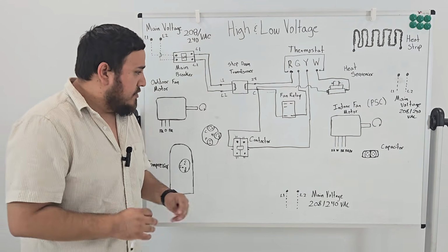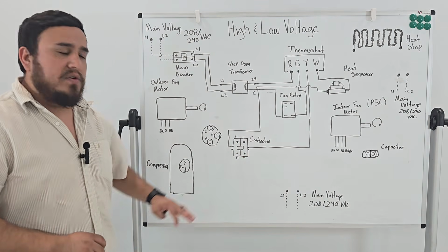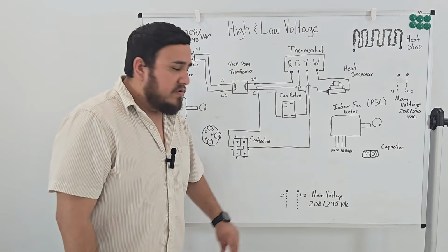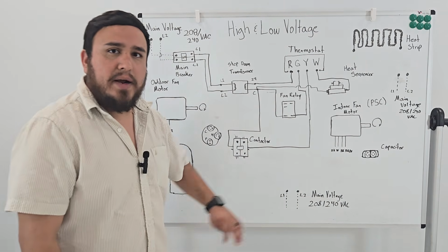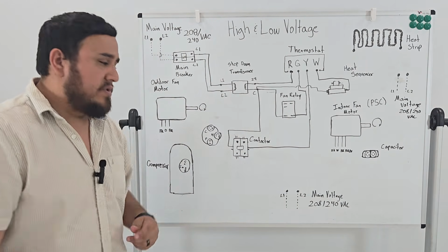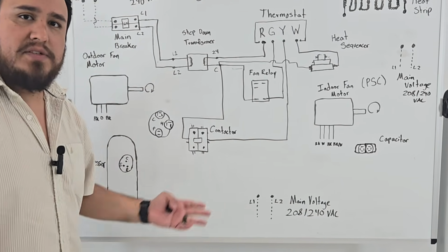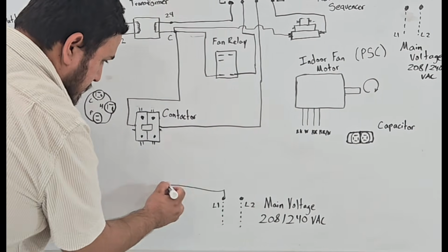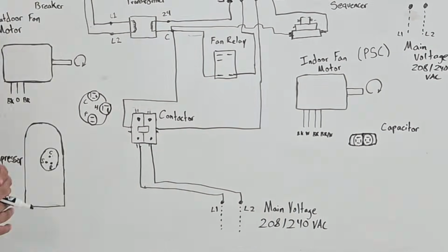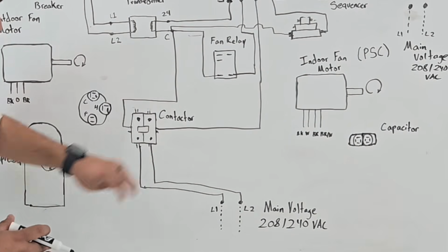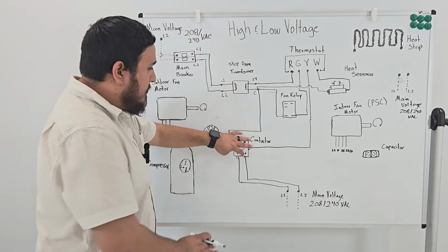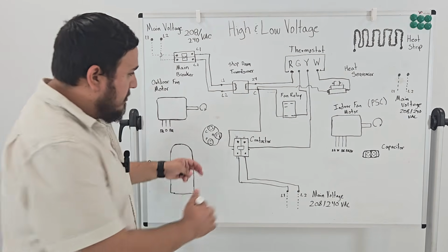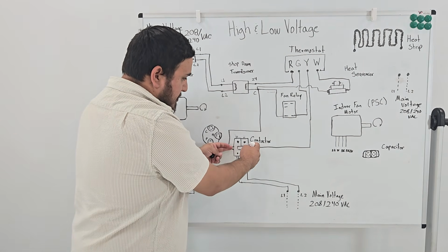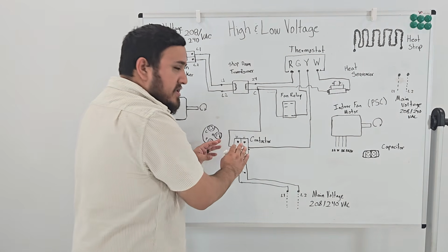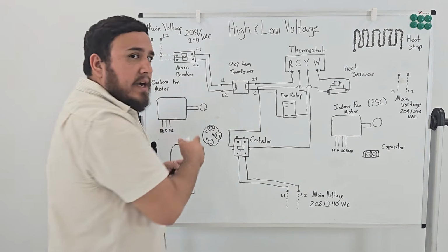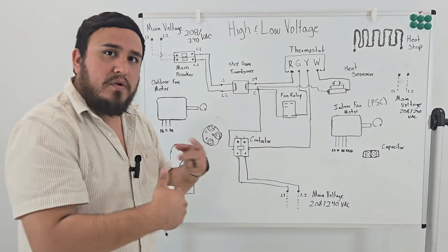Before I get started, let's provide voltage to my outdoor system. Right here, I have my main voltage, or in this case, my disconnect for my air conditioning system, for my condenser system. So let's supply that voltage to my contactor. Right, so that main voltage is already supplied to the contactor. Now I gotta send that high voltage to my loads. That means that whenever my low voltage is being sent to my contactor, it engages the contacts and sends that high voltage to my loads so they can function.